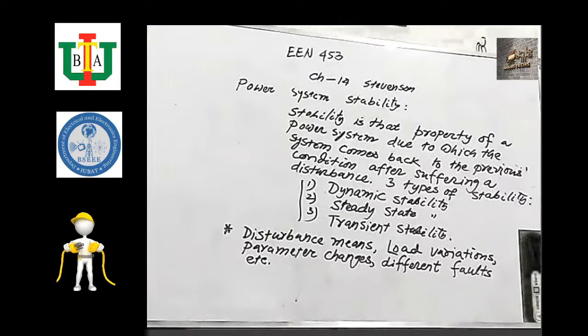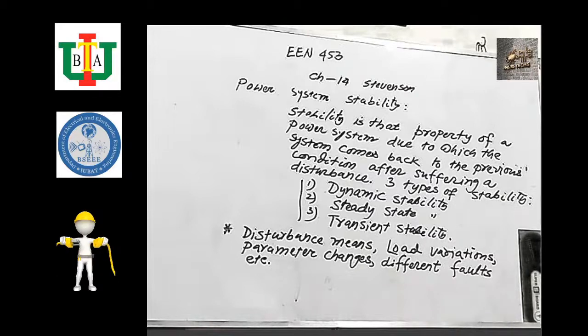In that case, the prime mover which is rotating the rotor may break down. Understand? So the high oscillation should be prevented or suppressed. For suppression of the high oscillation, there is damper winding in the machine. Third type of winding, damper winding. So in a large alternator, how many types of parts are there? Three types of parts. One is rotor, another is stator, another is damper winding.